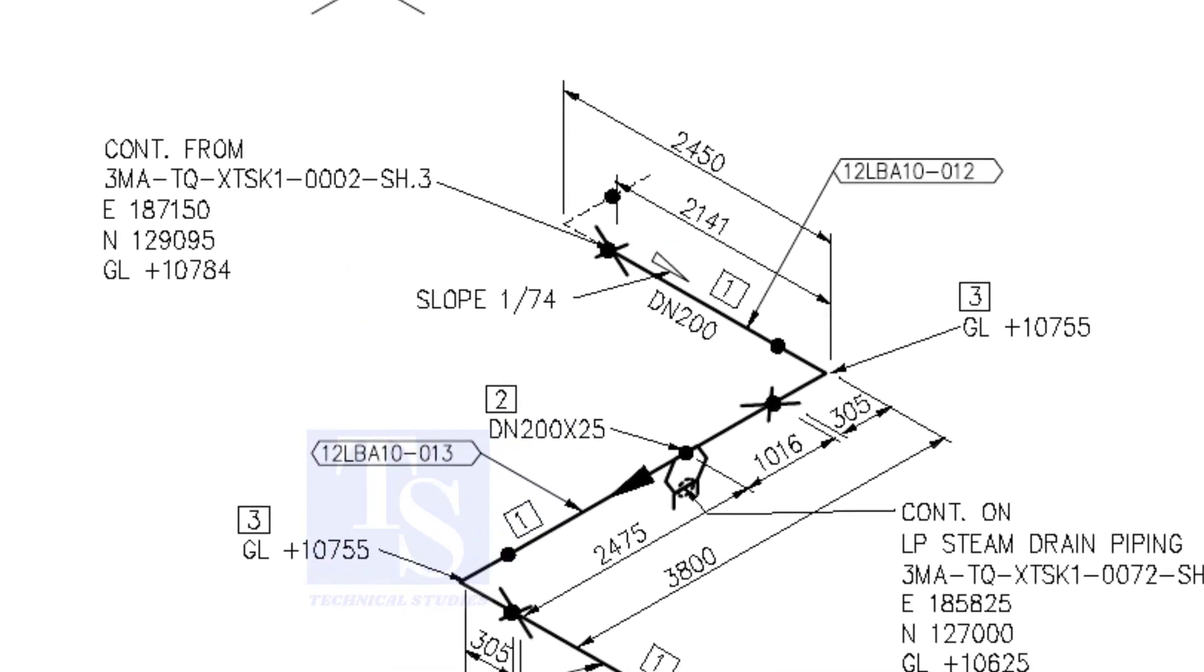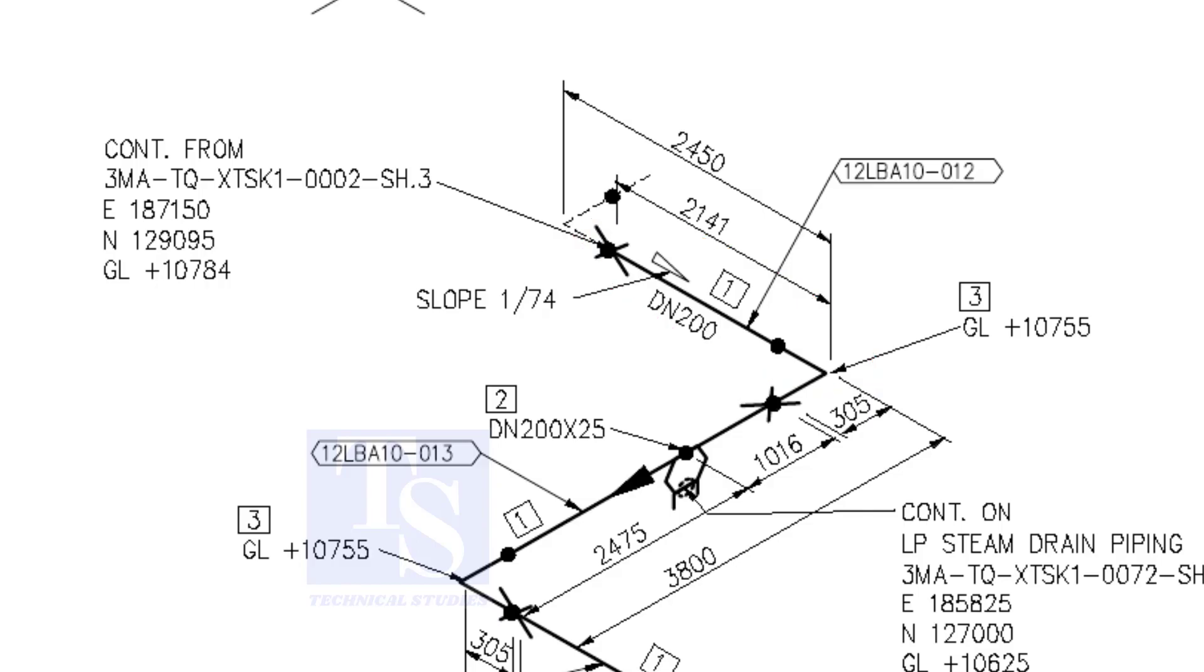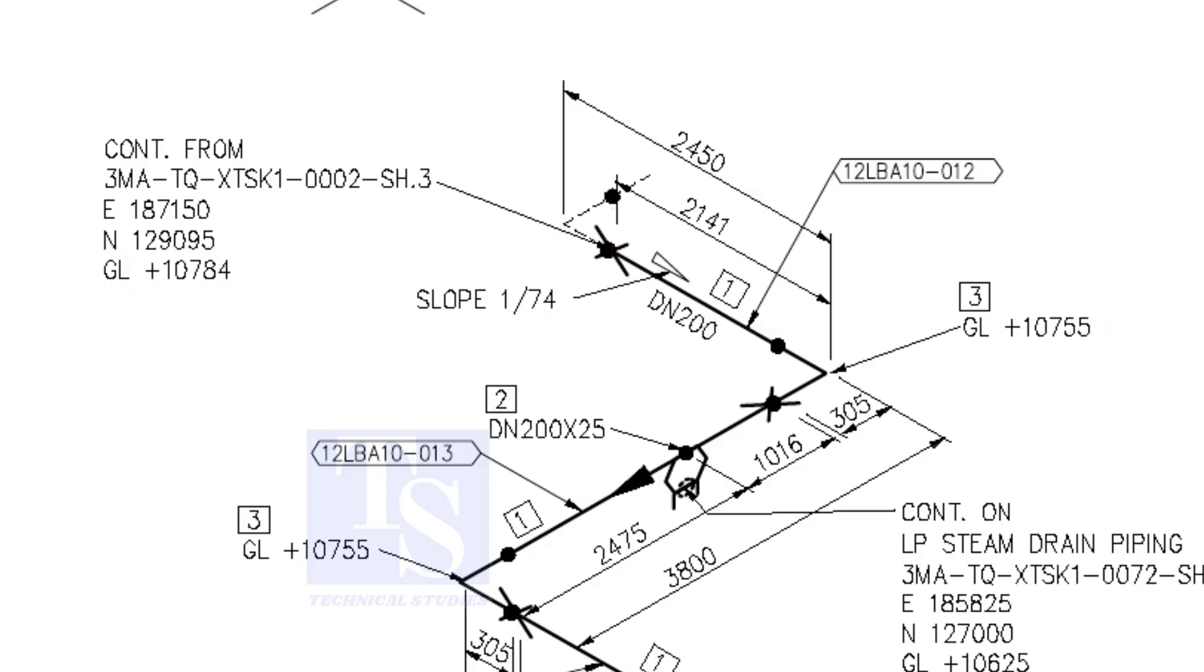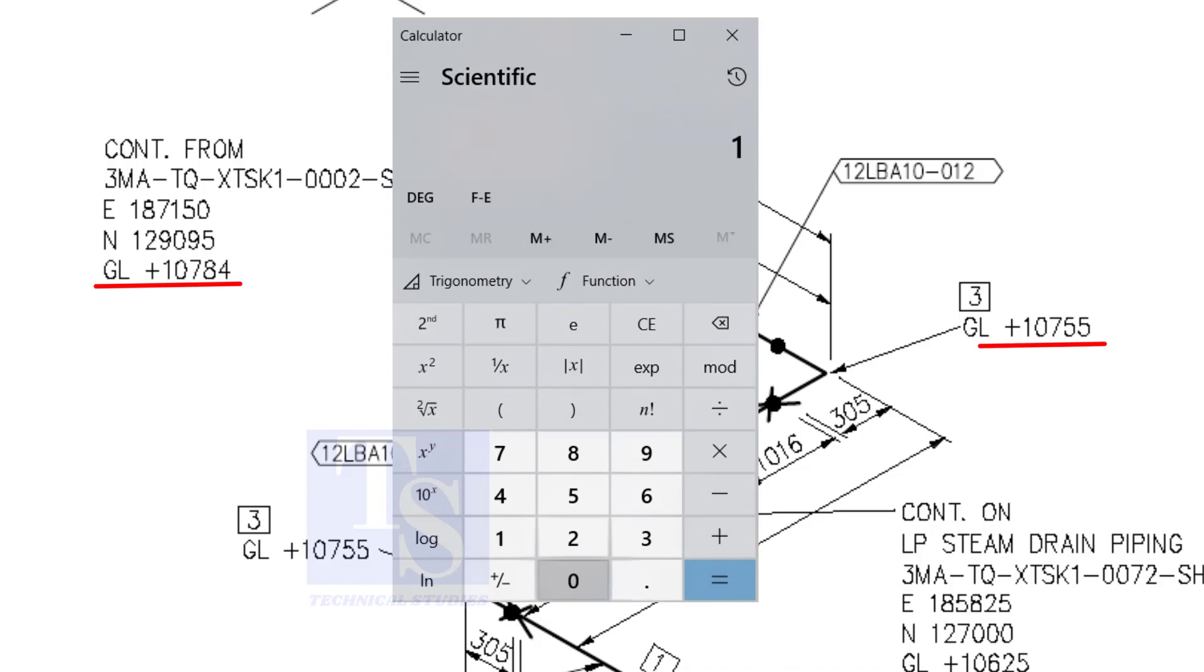Let us check the slope of this particular part of this piping. This is the higher point. And this is the lower point. 10,784 minus 10,755 equals 29 millimeters.